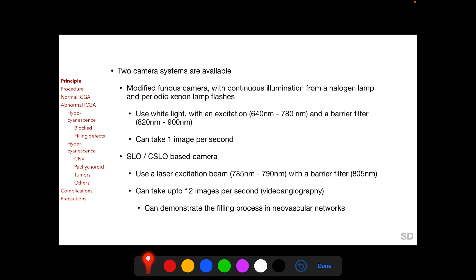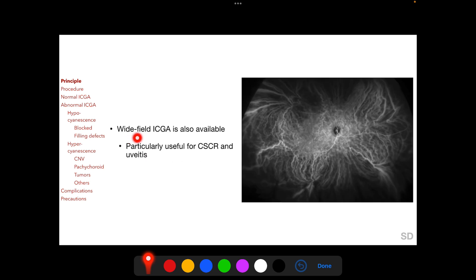Two camera systems are available for ICGA. One is a modified fundus camera using white light with an excitation and a barrier filter, which can take only one image per second. The other is a scanning laser ophthalmoscope (SLO) based camera, which uses a laser excitation beam with a barrier filter and can take up to 12 images per second — this is called video angiography. Wide-field ICGA is also available and is particularly useful for central serous chorioretinopathy and uveitis, where there can be diffuse involvement of the choroid.